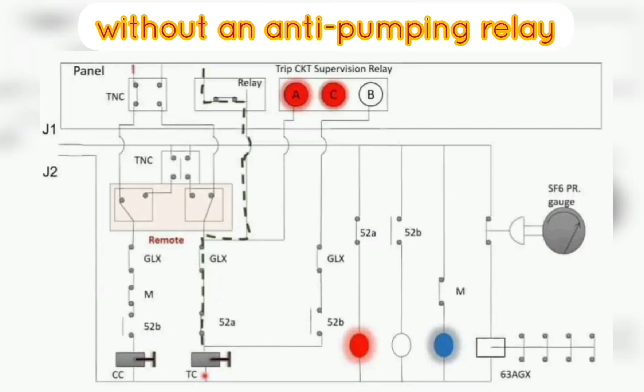Next we learn about how the anti-pumping relay prevents repetitive closing commands. The control circuit diagram of the circuit breaker without an anti-pumping relay is shown in the figure. If the TNC switch remains in a closed position due to any issue, or the operator keeps it in a closed position during fault conditions, both close and trip commands will remain in the circuit, causing repeated closing and tripping of the breaker. This type of operation will cause damage to the circuit breaker and power system because of the high magnitude of the fault current.